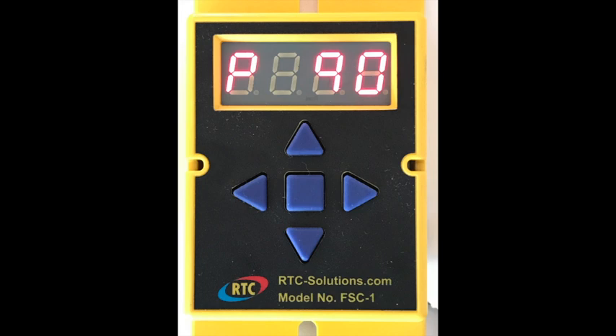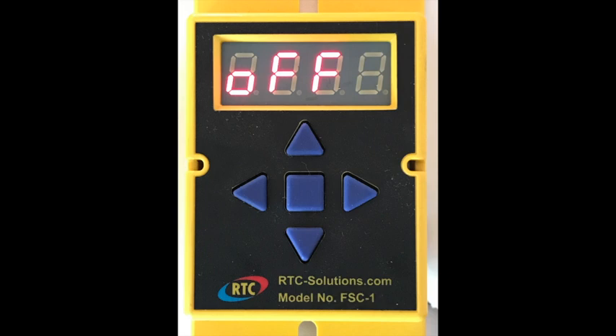Once the motor is started, the display will flash back and forth between the setpoint and the motor RPMs. If your display flashes between the setpoint and off, it means the controller is not receiving a feedback signal from the motor for RPMs, so it thinks the motor is stopped.